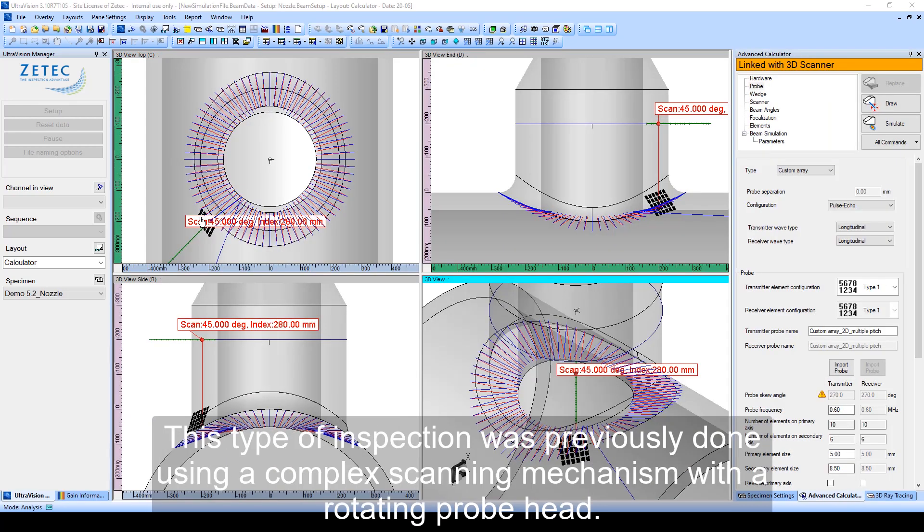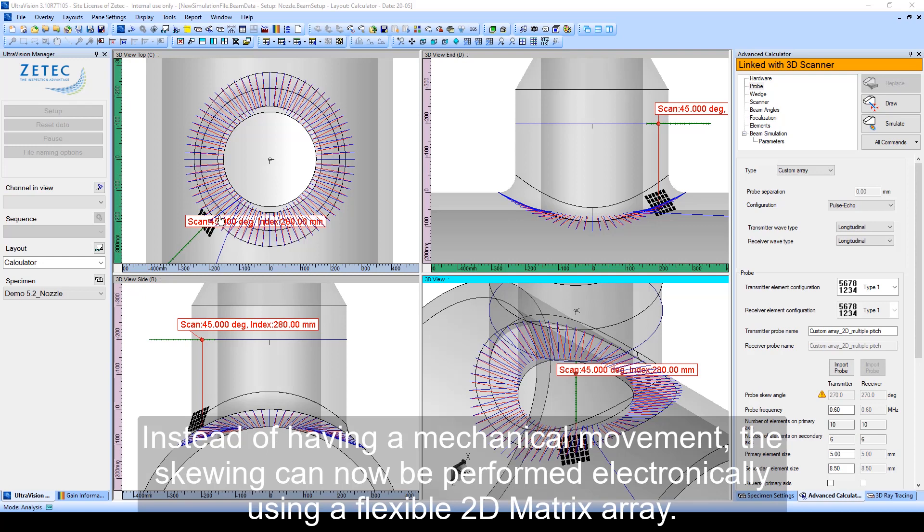This type of inspection was previously done using a complex scanning mechanism with a rotating probe head. Instead of having mechanical movement, the skewing can now be performed electronically using a flexible 2D matrix array.